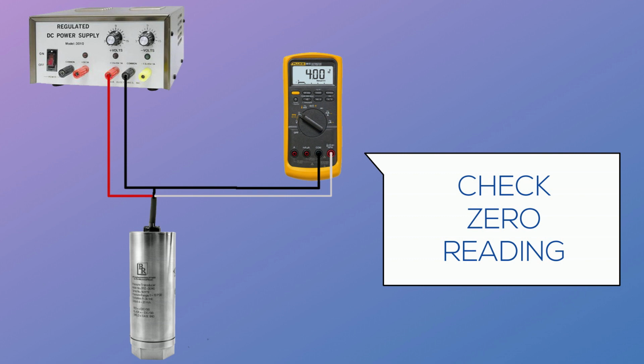If a zero adjust is available on the transmitter, the zero may be adjusted to within an acceptable limit now. If no zero adjust is available, verification of the zero reading is recorded and pass-fail criteria determines whether the unit needs to be sent back for recalibration or is within the acceptable limits of the unit being used. Again, in this example, that would be 4 milliamps plus or minus the factory zero balance tolerance.